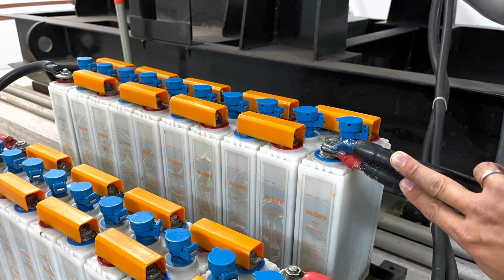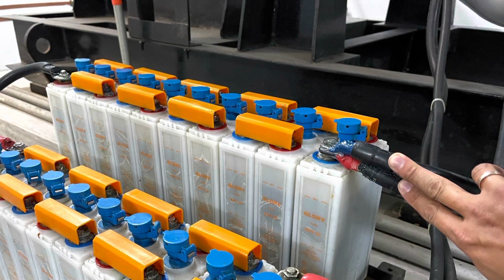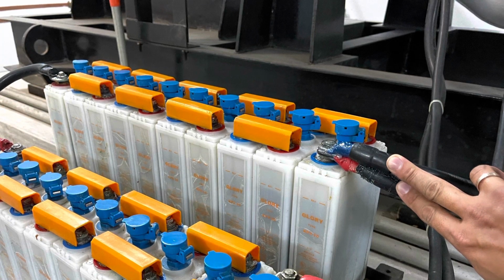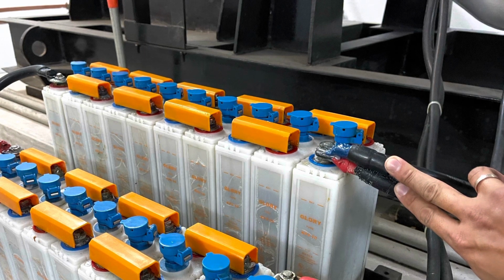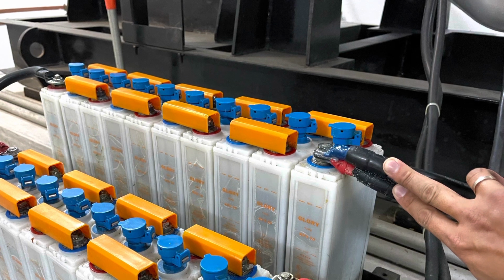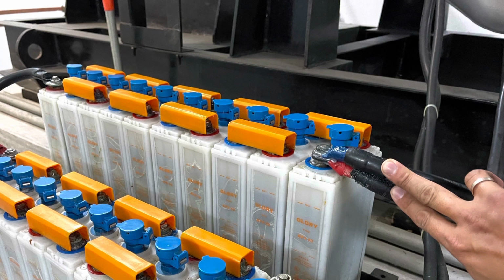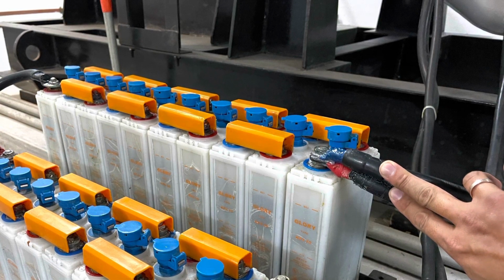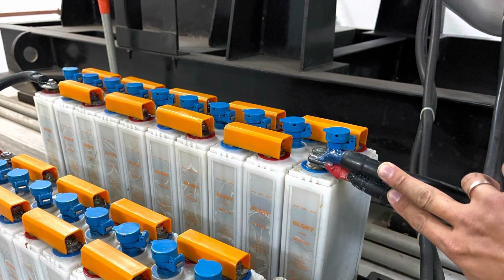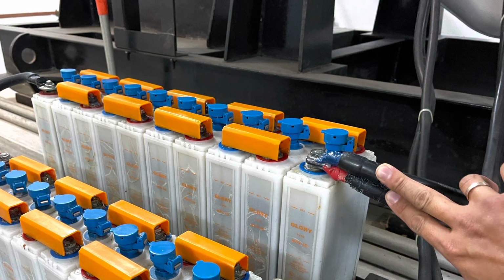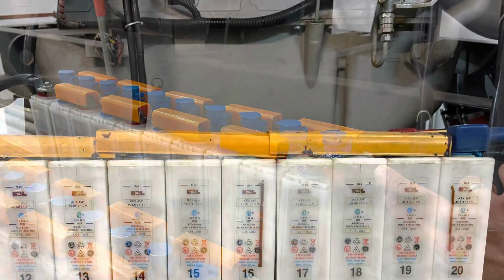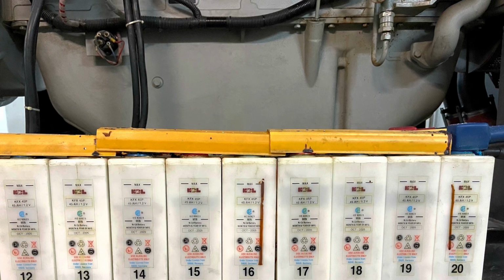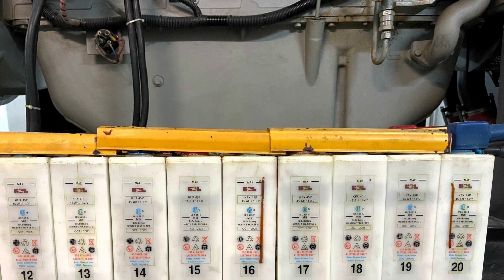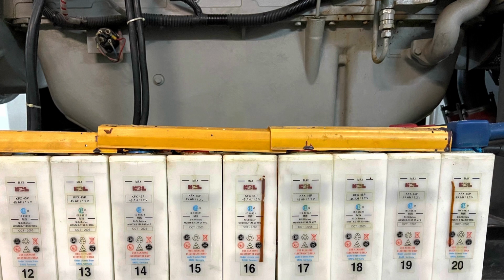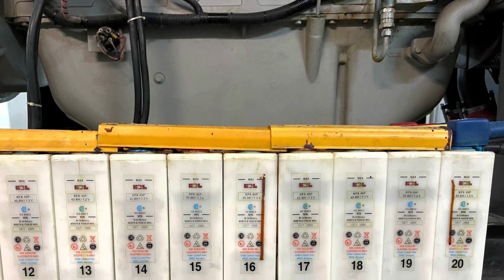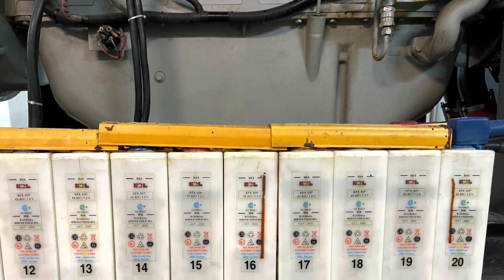So I hope this sharing can help you in your work, and in how you check the condition of your genset battery. My advice is you have to do this much more frequently, and as you do it more often, you will witness the genset battery voltage drop characteristic during cranking. The more you see the voltage drop characteristic, the pattern and the movement, the more you will learn when it is considered weak, or when it is considered strong or in good condition. So you have to do this more frequently. It's hard to tell by words; it's more about how you perceive the movement and motion of the voltage drop, and at what level the needle drops.